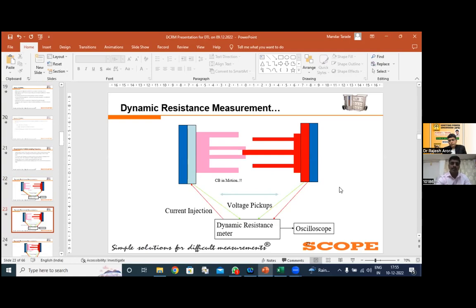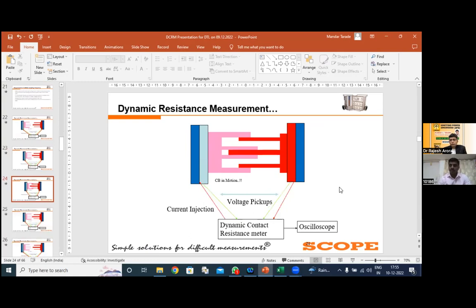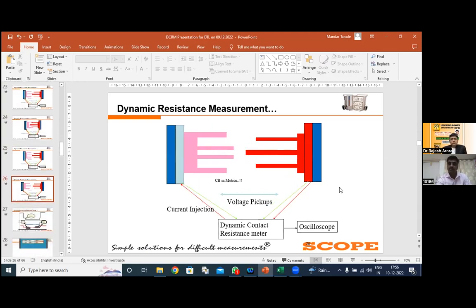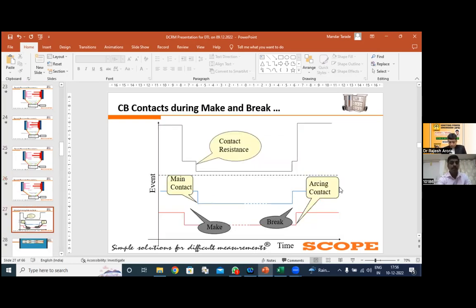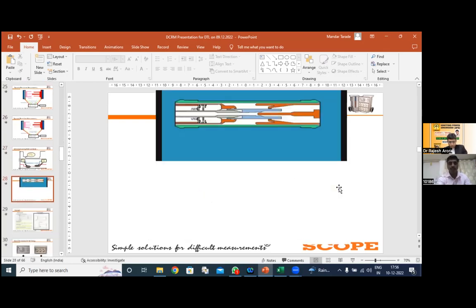This is just the graphical representation available on your screen. At the time of closing, first your arcing contact touches and quenches the arc, then your main contact touches and establishes the contact. At the time of tripping, first your main contact releases and then your arcing contact releases. Accordingly, we get the graph or plot of the DCRM. Here I have given the timing trace as well as the arcing contact and the main contact in graphical representation.